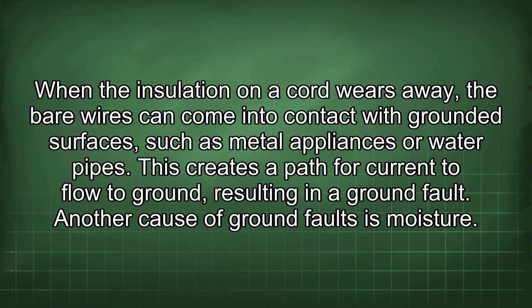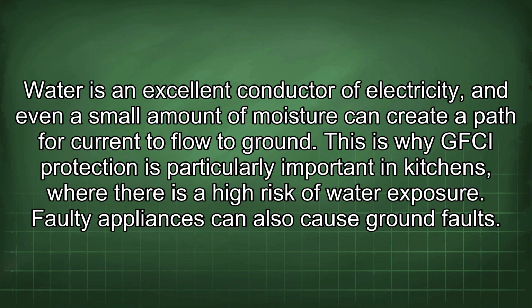Another cause of ground faults is moisture. Water is an excellent conductor of electricity, and even a small amount of moisture can create a path for current to flow to ground. This is why GFCI protection is particularly important in kitchens, where there is a high risk of water exposure. Faulty appliances can also cause ground faults.